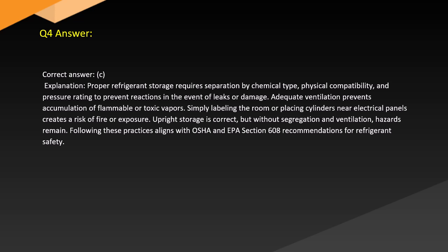Correct answer: C. Proper refrigerant storage requires separation by chemical type, physical compatibility, and pressure rating to prevent reactions in the event of leaks or damage. Adequate ventilation prevents accumulation of flammable or toxic vapors. Simply labeling the room or placing cylinders near electrical panels creates a risk of fire or exposure. Upright storage is correct, but without segregation and ventilation, hazards remain. Following these practices aligns with OSHA and EPA Section 608 recommendations for refrigerant safety.